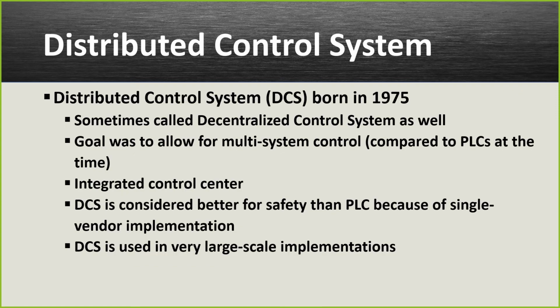Another system we have is the distributed control system, or DCS, also sometimes called a decentralized control system. It was born a little later, in 1975, with the goal of allowing multi-system control compared to PLCs at the time. Back in the 1970s, PLCs were really kind of one-off units—this PLC controls this system, this one controls this other system—with really no communication between PLCs or centralized management of them at first.